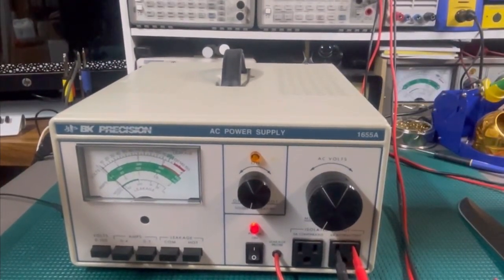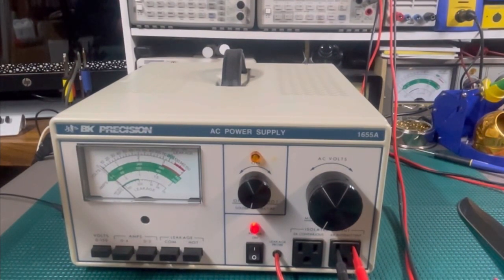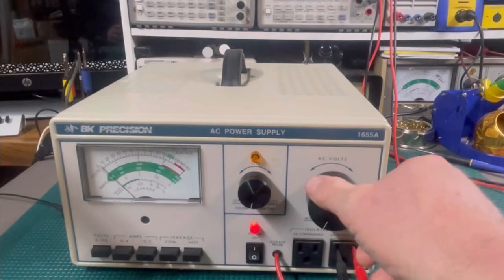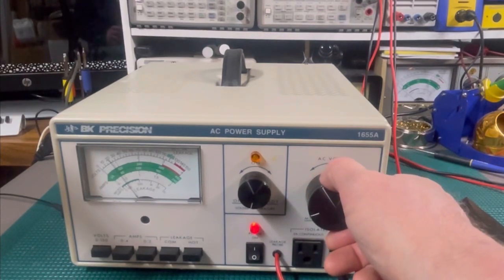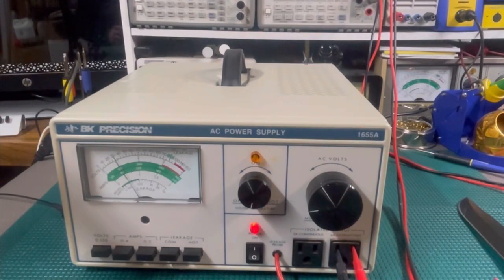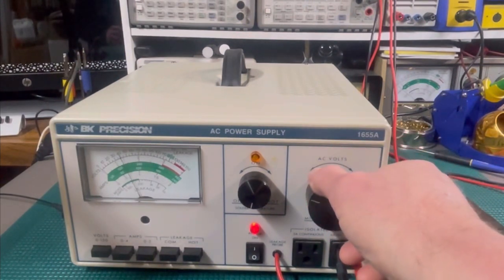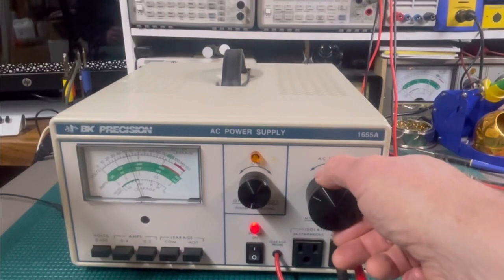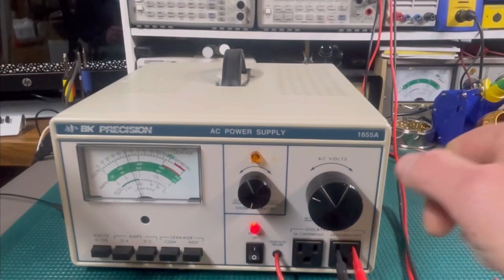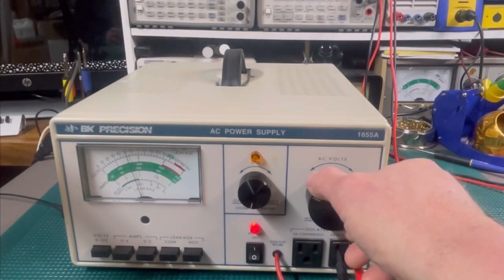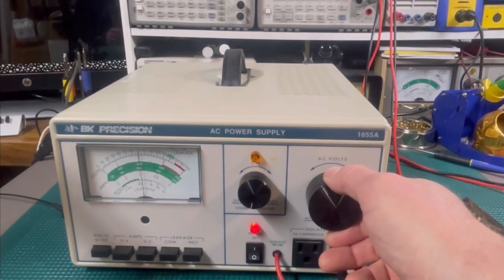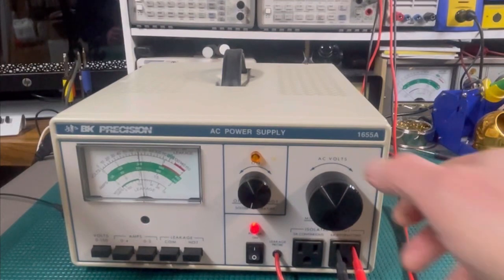Okay. All right. So we have that second voltmeter plugged in to this device under test isolator, and we'll slowly bring up the voltage. Let's go to 30 volts on the machine. Not too bad. Agilent's reading 26. Go up to 50. Overshot a bit. Let's see, about 50. Okay, 44. So we're not quite linear, but 70, 61, yeah. So interesting.